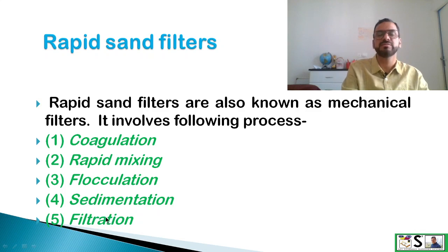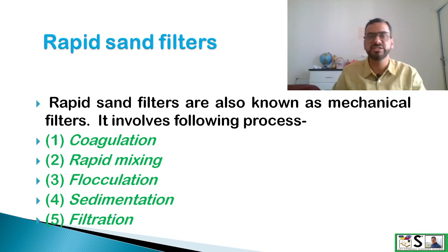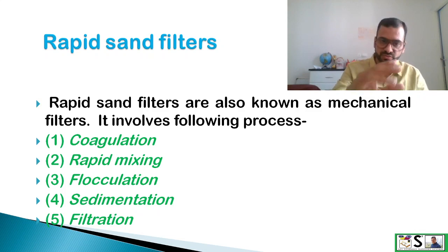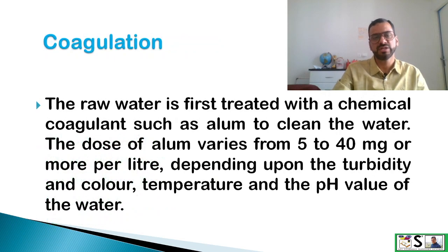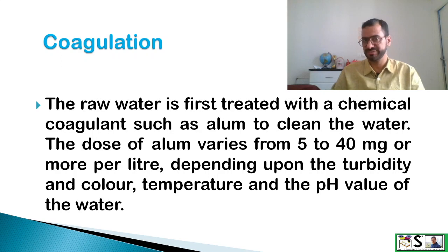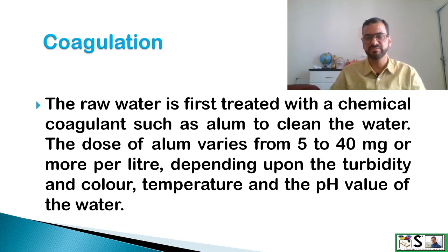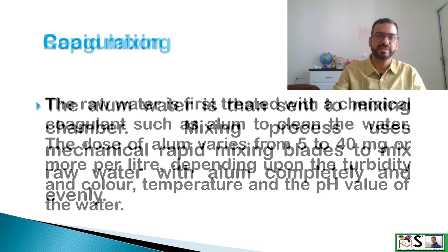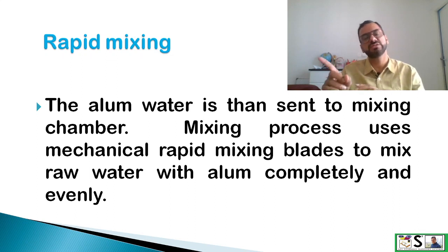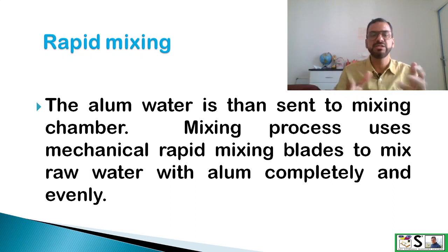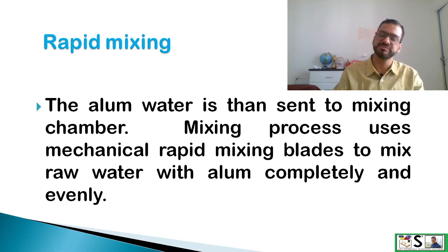After the sedimentation stage, the remaining process is the same as in slow sand filters. The raw water is first treated with a chemical coagulant such as alum. The dose of alum varies from 5 to 40 mg or more per liter depending on turbidity, color, temperature, and pH. The alum water is then sent to the mixing chamber where mechanical rapid mixing blades mix the raw water with alum completely and evenly so that alum can act for coagulation.